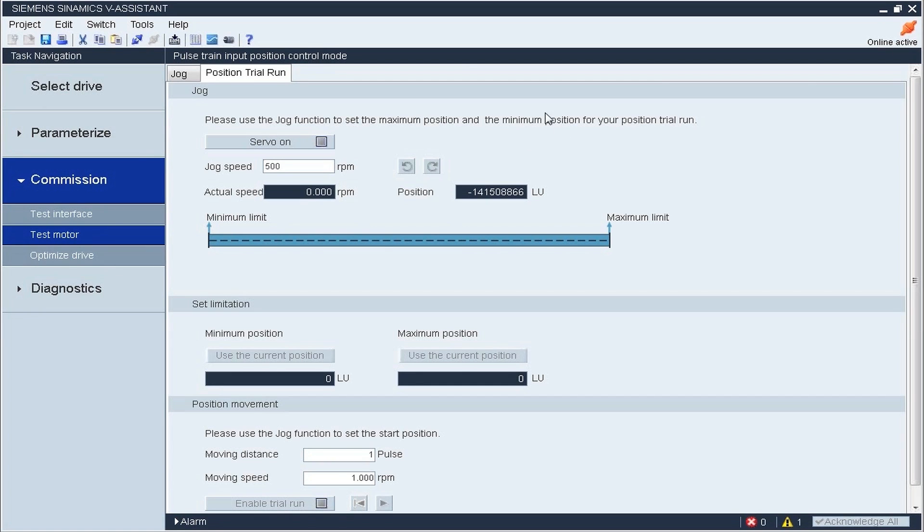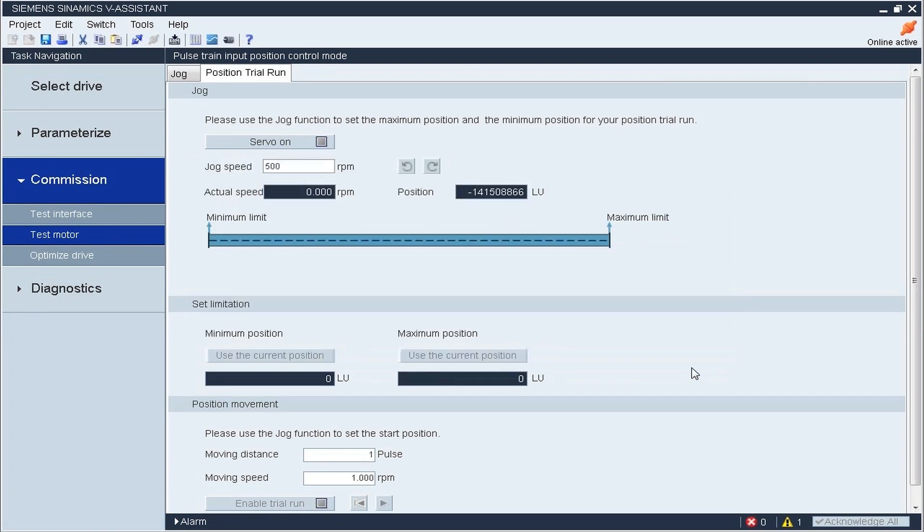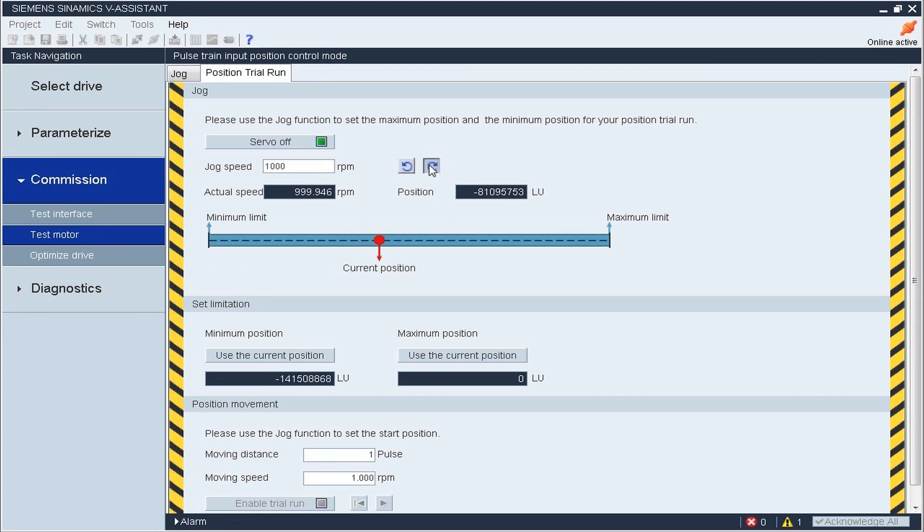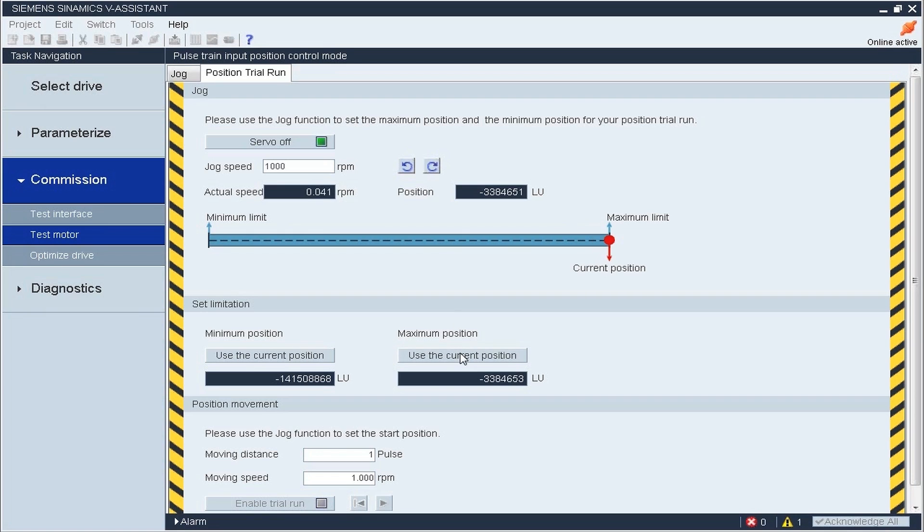When starting POSITION TRIAL RUN operation, we first have to set the minimum and maximum distance that the motor can move when jogging. We use the actual position as minimum position and jog the motor forward to the next position as maximum position.